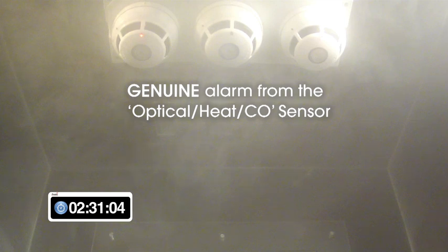After approximately 2 minutes 28 seconds, the optical heat CO sensor produces an alarm condition. This is because a true fire condition has created a combination of smoke which is seen by the optical channel, a small amount of heat which is seen by the heat sensor channel, and most importantly a relatively high amount of carbon monoxide which is monitored by the carbon monoxide sensing element. It is the combination of the amount of each phenomenon created over the specific time period that has allowed the algorithms controlling the alarm-making decision to produce the genuine alarm condition.